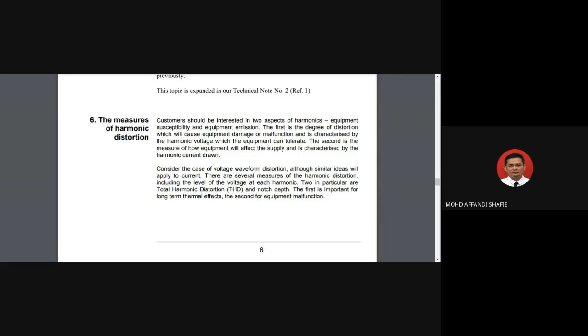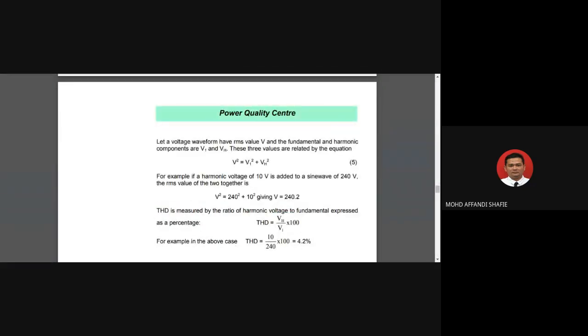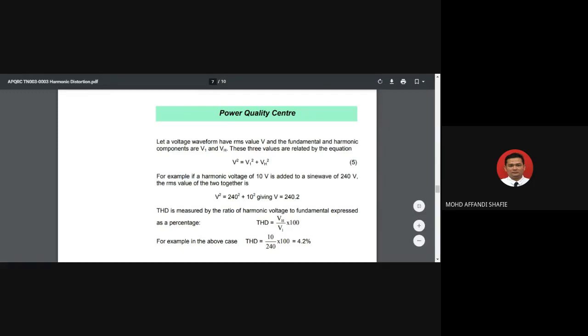Okay, so for the long-term thermal effect, this one is total harmonic distortion, THD, and then for the equipment malfunction, we refer to the other one. Let a voltage waveform have RMS value V, and the fundamental and harmonic components V1 and Vh. So these three values are related by the equation: V squared equals V1 squared plus Vh squared.